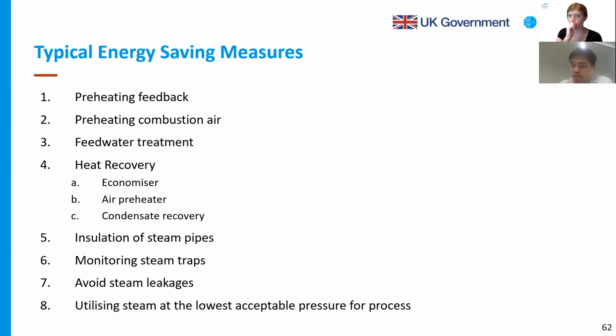For typical energy saving measures, I think previously Karthik already explained the typical ESM for thermal use. For example, preheating the feed water and preheating the combustion air. Number 3 is feed water treatment to soften the water. Heat recovery is the most important among all, because the flue gas energy loss can typically be up to 12% in the boiler heat process. Number 5 is installation of steam pipe insulation, and number 6 is monitoring the steam traps, avoiding steam leakage, and utilizing steam at the lowest acceptable pressure for the process. Next slide.